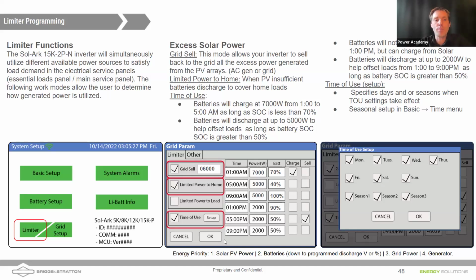Well, we can do that by programming the inverter's limiter. And the limiter allows us to control how much power flows to and from batteries during different times. So there are a couple of things that we can do with the limiter. We can do something called grid sell, and grid sell is exactly what you would think. It would be how much power you're going to allow the inverter to sell back to the grid.